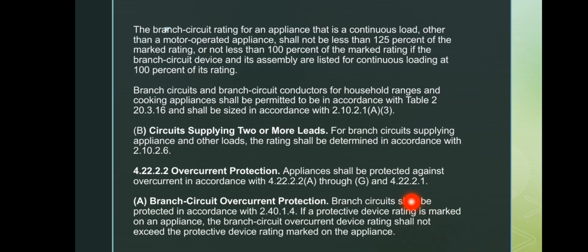For household range and cooking appliances, we can follow Table 220.55, and the conductor sizes must meet the requirements of 210.19(A)(3). If the branch circuit supplies two or more loads, then the circuit ratings must follow the rules in 210.23. Next is the overcurrent protection.